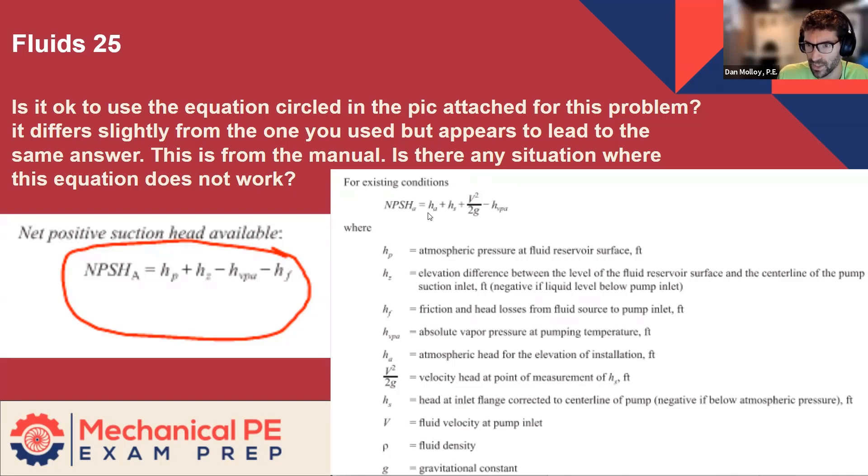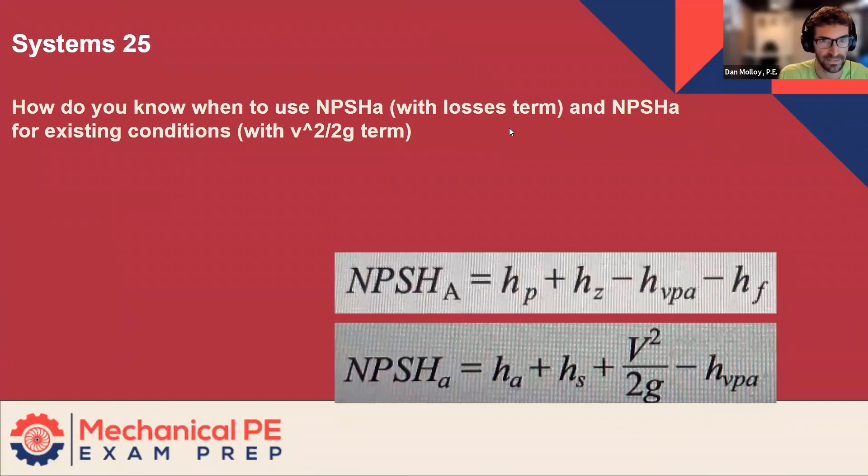I think what you're driving at is: can we use this other one, are they the same, when do we use which one? So hold that thought. The second question is more directly asking that very thing: how do you know when to use NPSHA with the losses term, which is the design version, versus NPSHA for existing conditions? So we have design versus existing conditions. How do you know which one you're dealing with? Well, it depends on the information that's given. Maybe we can draw a little picture and annotate this.